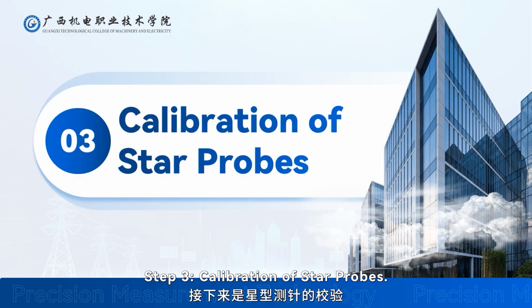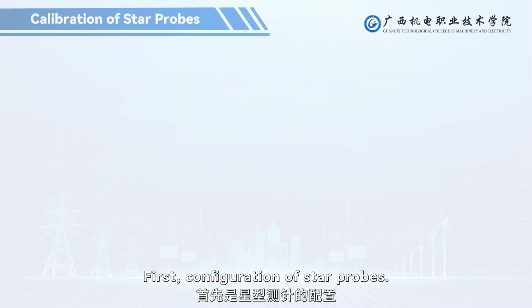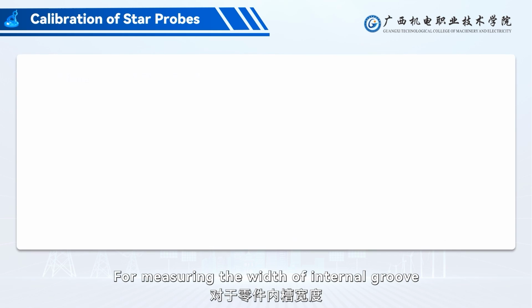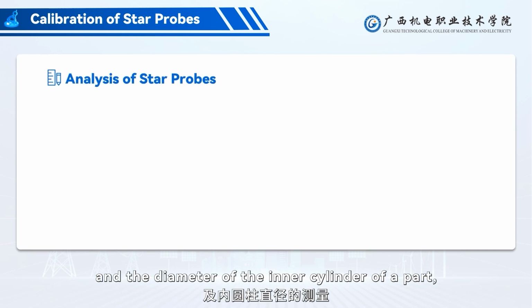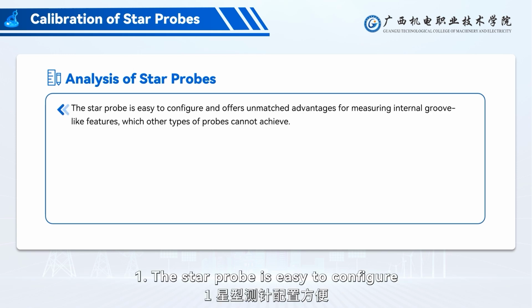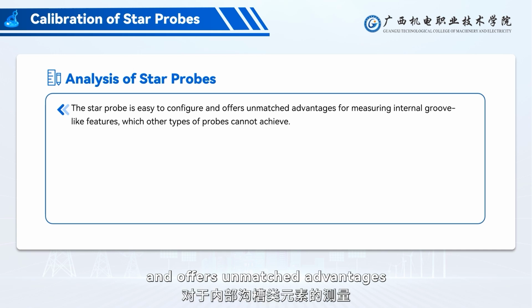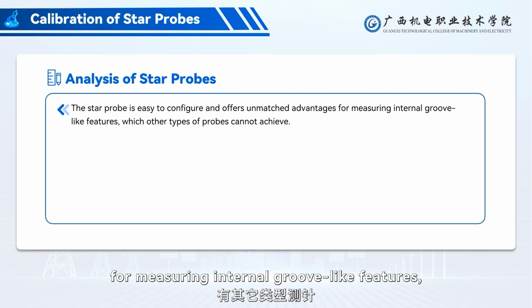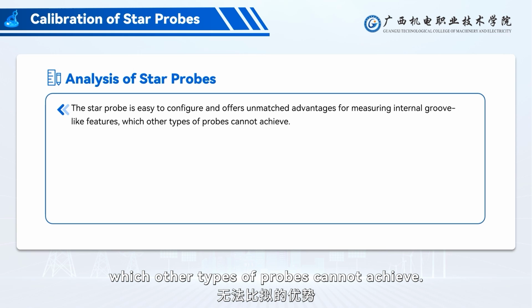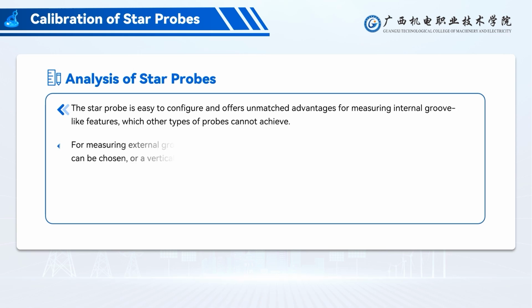Step 3. Calibration of star probes. First, configuration of star probes. For measuring the width of internal groove and the diameter of the inner cylinder of a part, the star probe is the optimal measurement solution. 1. The star probe is easy to configure and offers unmatched advantages for measuring internal groove-like features, which other types of probes cannot achieve.